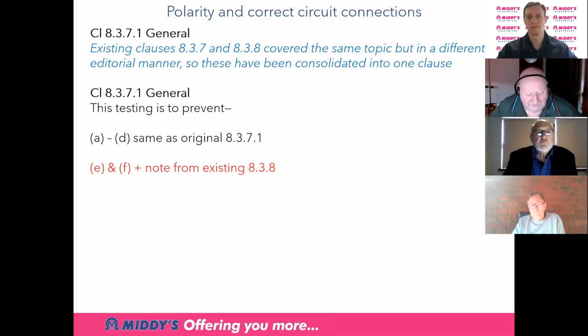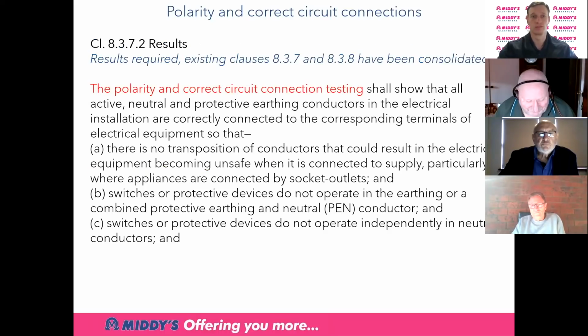Okay, so what we've basically done is A to D of our polarity have remained exactly as they were. And then we've taken the E and F notations or clauses from the correct circuit connections and placed them in with the polarity. And the title now is Polarity and Correct Circuit Connections, which to me makes a lot of sense. Hope it does to you. Next slide, please. So as a result, the results now come down to being for polarity and correct circuit connections that there's A, B, C, and D. If you read the words there, the only correction is in the first line there, the polarity and correct circuit connection testing. All the rest in black remains the same.